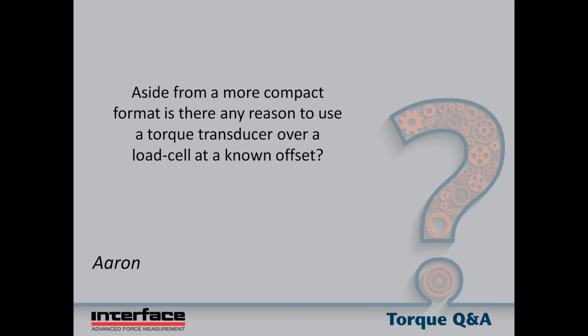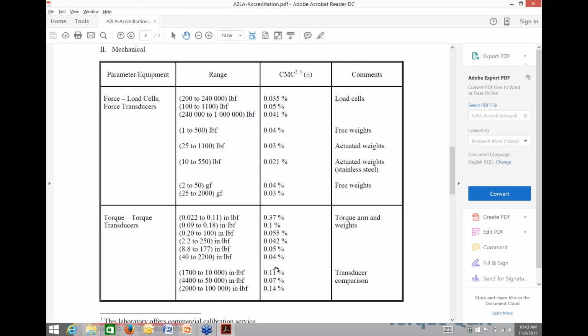The downside is that in packaging, it's easy to understand how you could measure torque using a torque sensor. To do the same using a load cell, you have to somehow apply or react a force at a distance off center, which in certain situations is quite easy if the device is, say, gimbaled. And I have a picture I can show you of a dynamometer that actually uses that scheme.